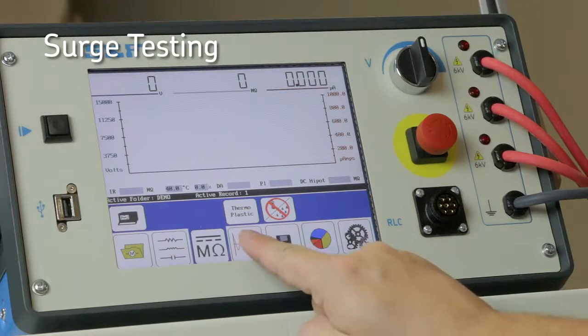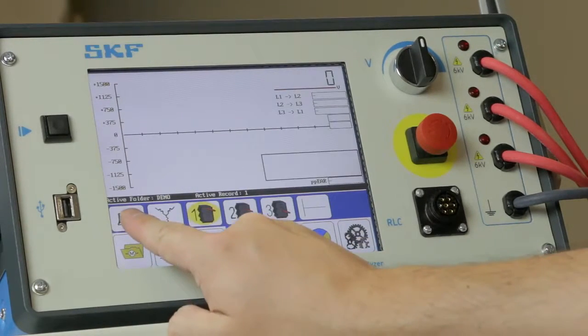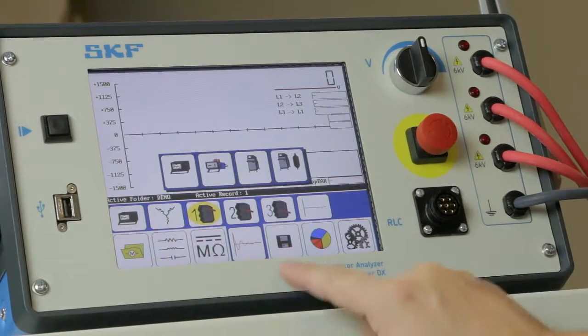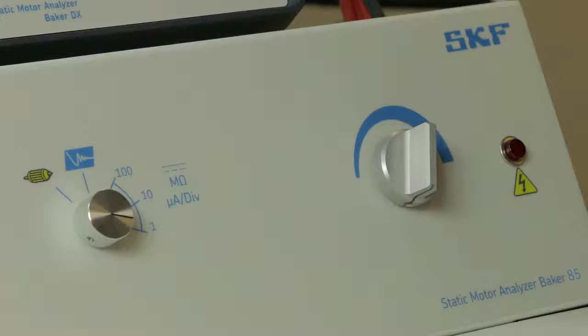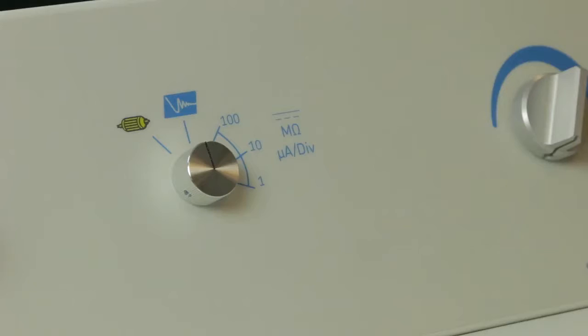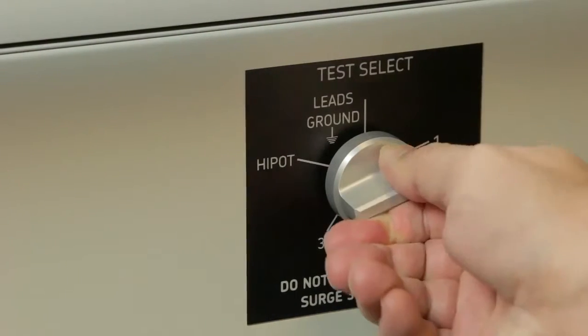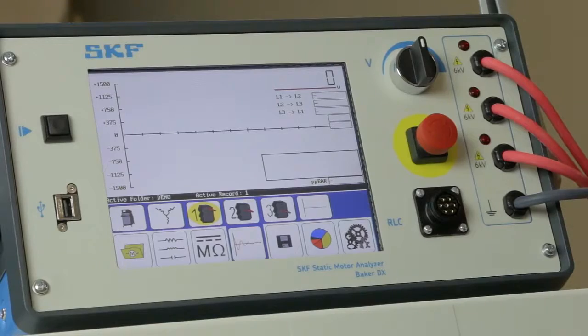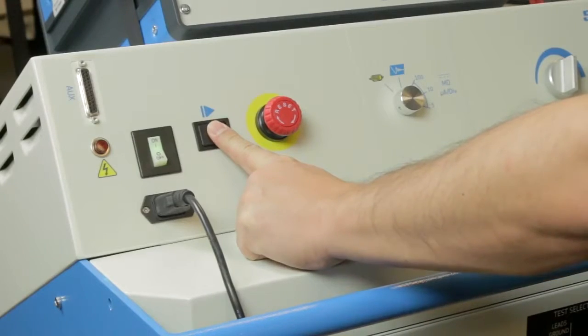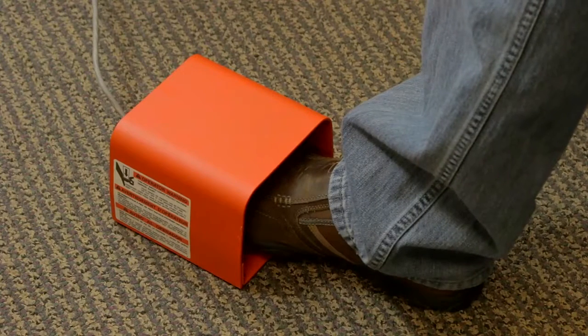On the main screen of the DX, select the surge test. Select the power pack. Verify that the voltage control knob is set to 0. Turn the power pack's function switch to the surge test position. Turn the test select knob to lead 1 and check that lead 1 is highlighted in yellow on the DX. Press and hold the push to test button or foot switch if connected.